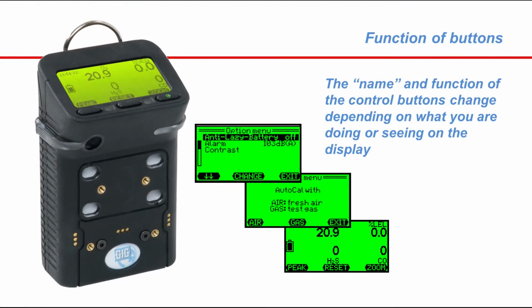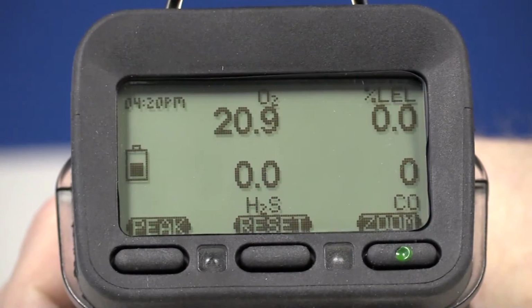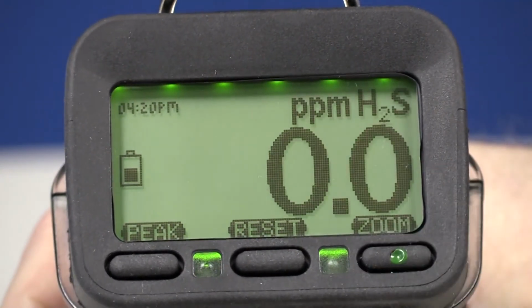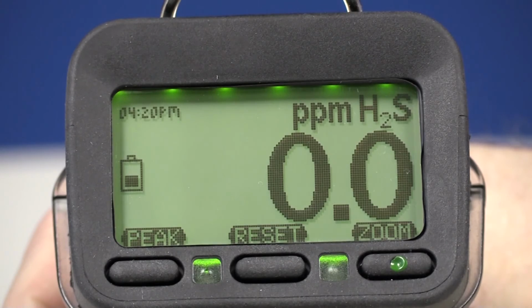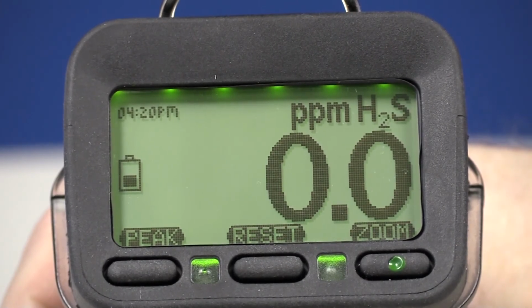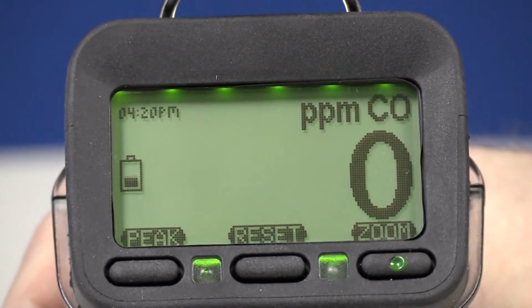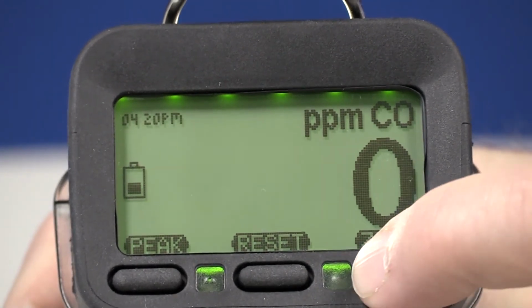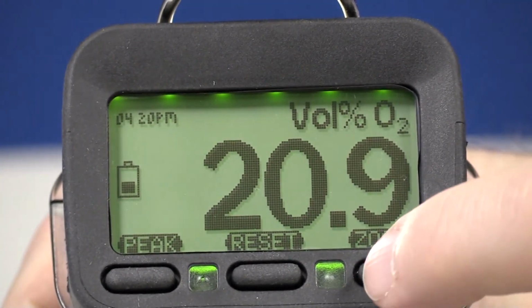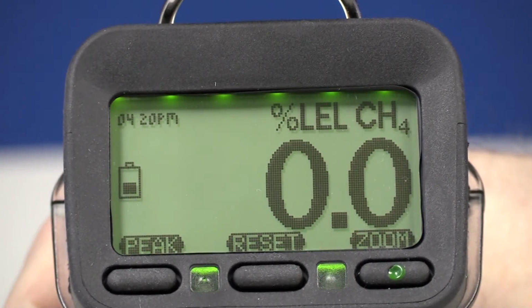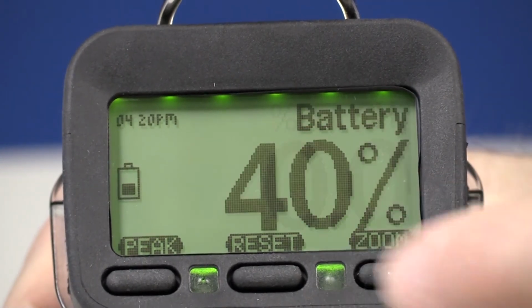The 3 buttons used to operate the instrument are soft keys. This means the name and the function of the button changes as a consequence of what you are doing or seeing in the display at that moment. In normal operation, the left-hand peak button is used to activate the peak hold mode operation feature. The center reset button is used to acknowledge or reset readings and alarms, and the zoom button is used to make the numbers larger, making them easier to read.